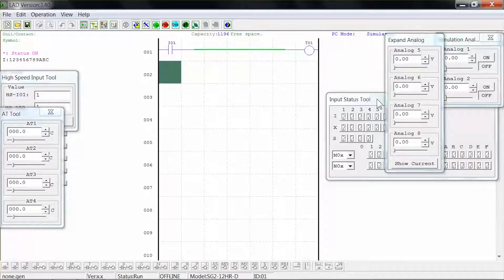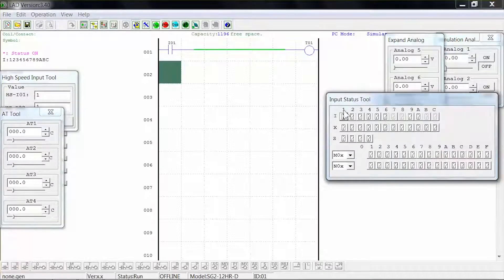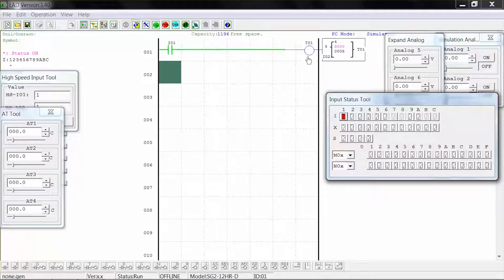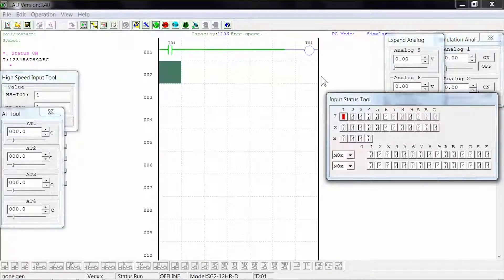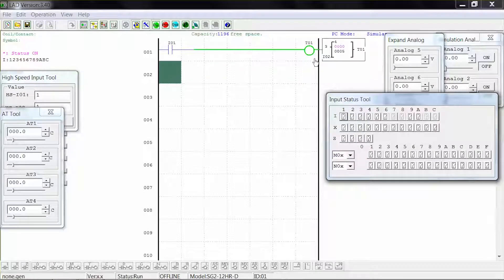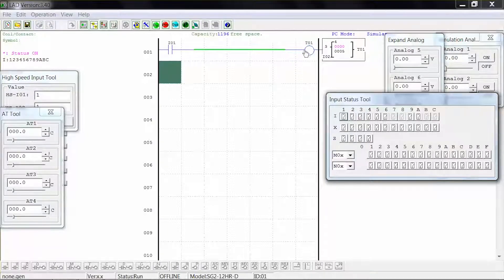On the input status tool window, close input 1. Note that this time the coil remains deactivated and the timer does not start counting. When we open input 1, the coil activates and the timer begins to count. When it reaches 5 seconds, the coil deactivates.